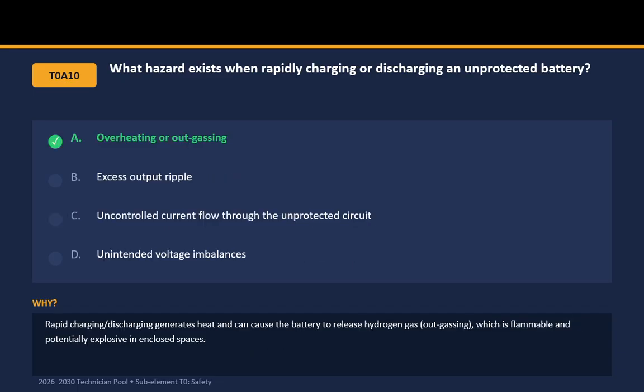What hazard exists when rapidly charging or discharging an unprotected battery? A. Overheating or outgassing. Rapid charging or discharging generates heat and can cause the battery to release hydrogen gas, or outgassing, which is flammable and potentially explosive in enclosed spaces.